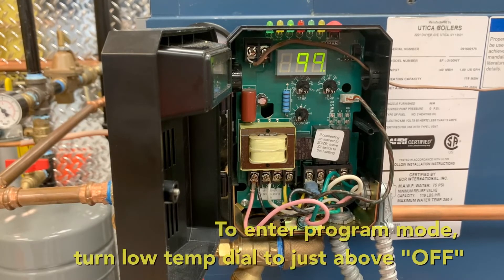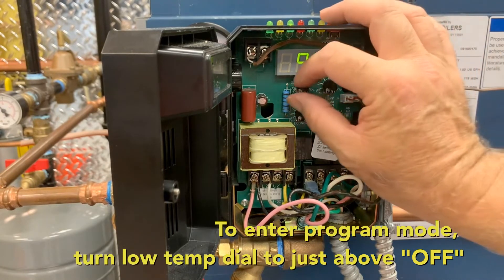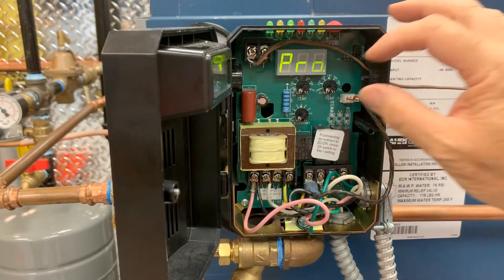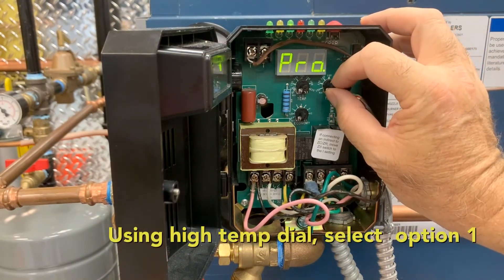To activate thermal pre-purge, enter the program mode by turning the low temp dial to a position just above OFF. This will be indicated by PRO on the screen. Then using the high temperature dial, select option 1.